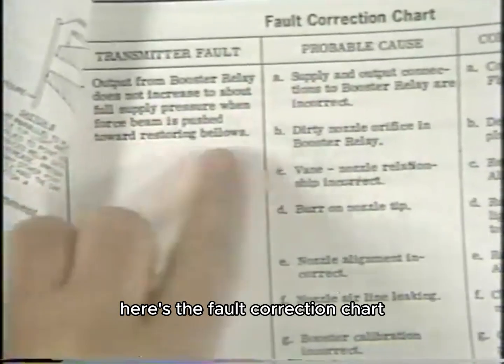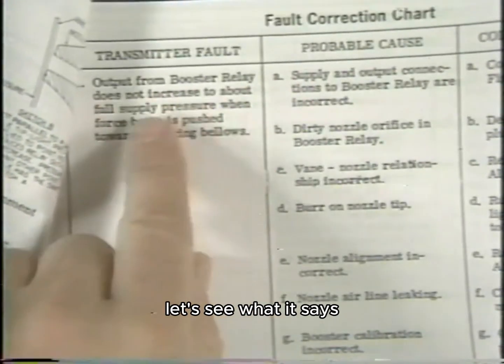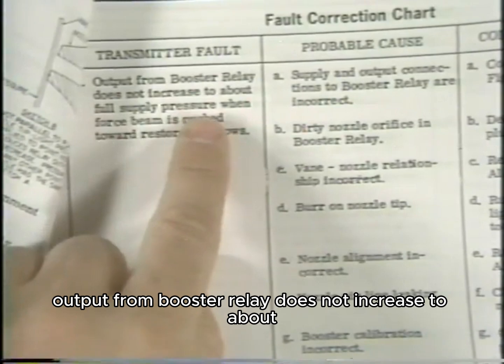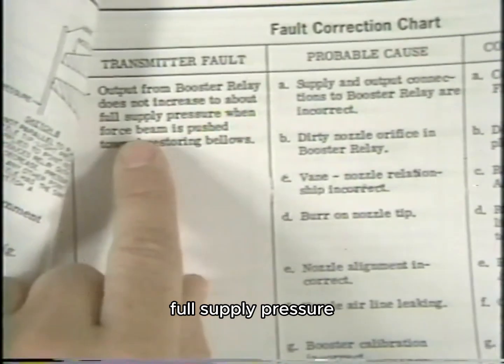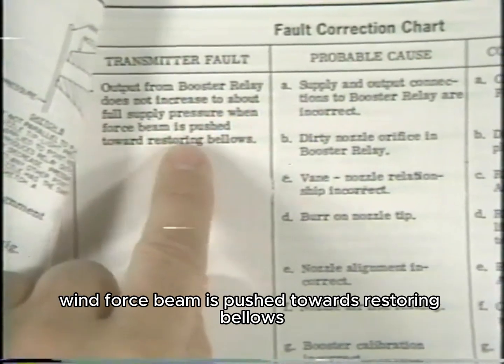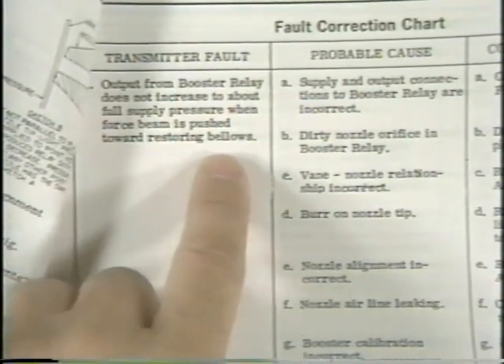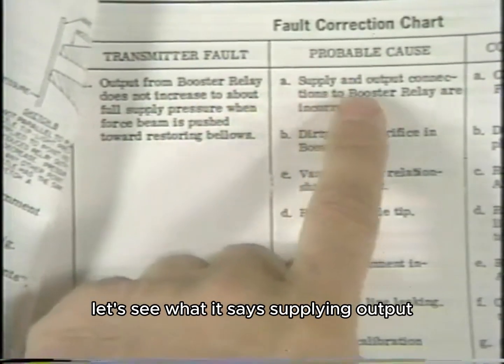There's a number of procedures in here that I can follow in making checks to the transmitter while I'm trying to find its problem. Here's the fault correction chart. Let's see what it says. Output from booster relay does not increase to about full supply pressure when force beam is pushed towards restoring bellows. Let's see what it says.